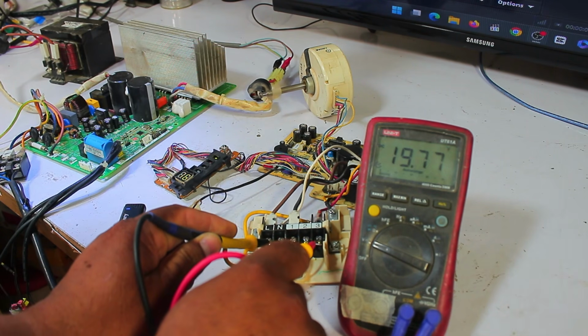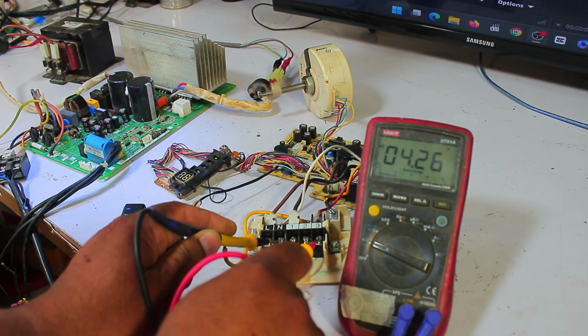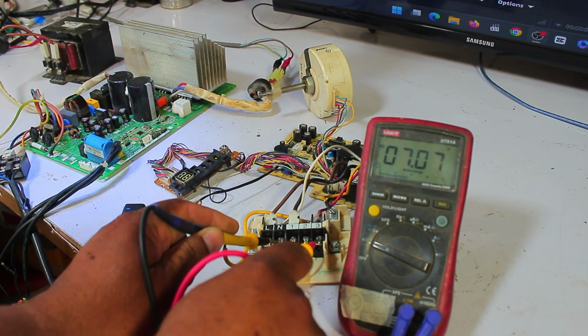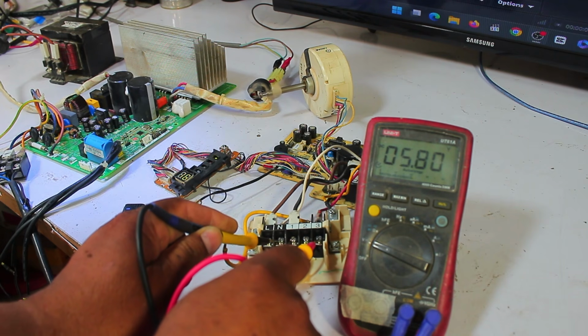So we will place one probe on neutral and the other probe on the communication wire. Look here, we are getting proper fluctuation. When this kind of fluctuation is present, normally it means the communication is okay.